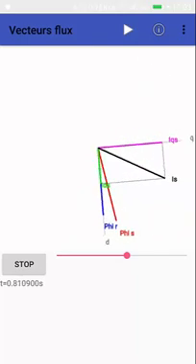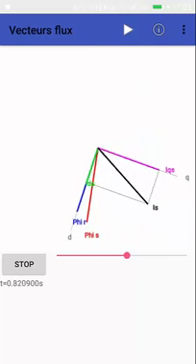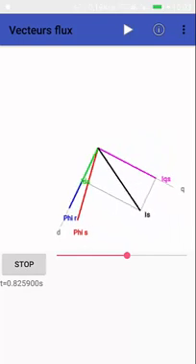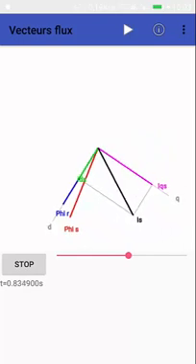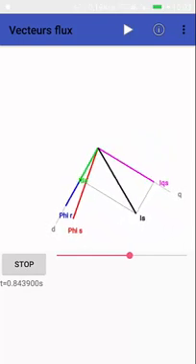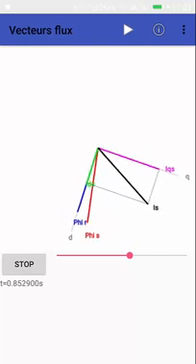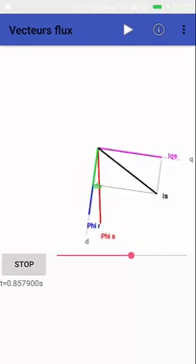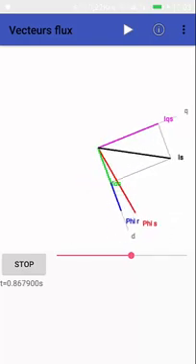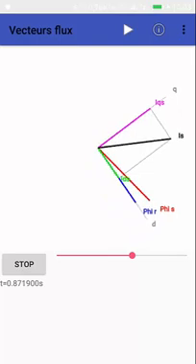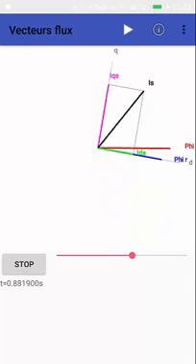You can see here there is an IQS responsible for the torque of the machine, and now the speed is reversing. We see the internal angle between the two vector flux - the stator flux is leading the rotor flux. We can also add and modify the events.